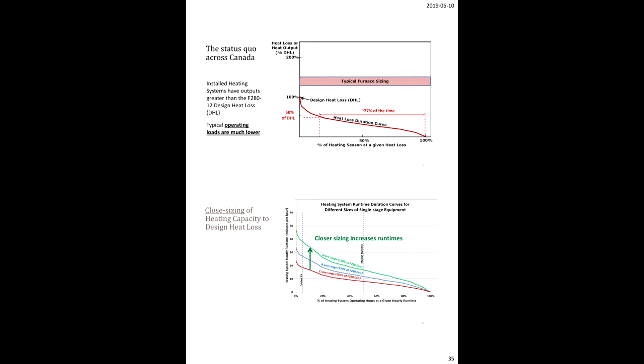We know that the equipment we put in is most likely going to run at part load for the vast majority of the year. So we need systems that can be variable in their operation with good turndown ratios, as the old term goes. I'll give you an example: if you really oversize a furnace for air heating, you're going to get a system that runs maybe 10 minutes on average per hour. But if you get closer to right-sizing it, you can double the runtime, which is important for delivering the system air.